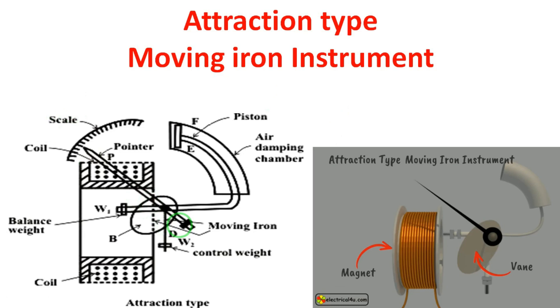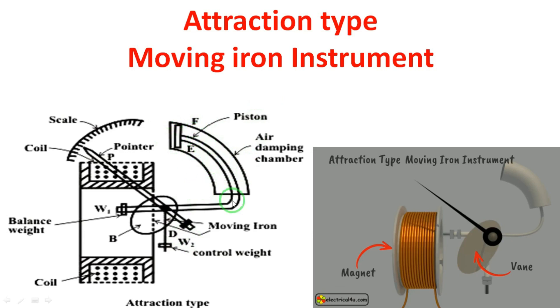In this instrument, we have three torques. First is the deflecting torque — this moves the pointer across the scale. Second is the control torque, which has two types: spring control torque and gravity control torque. We use a control weight and a balancing weight for gravity control. Third is the damping torque, which has three types: air friction damping, fluid friction damping, and eddy current damping. In this diagram, air friction damping and gravity control are used.